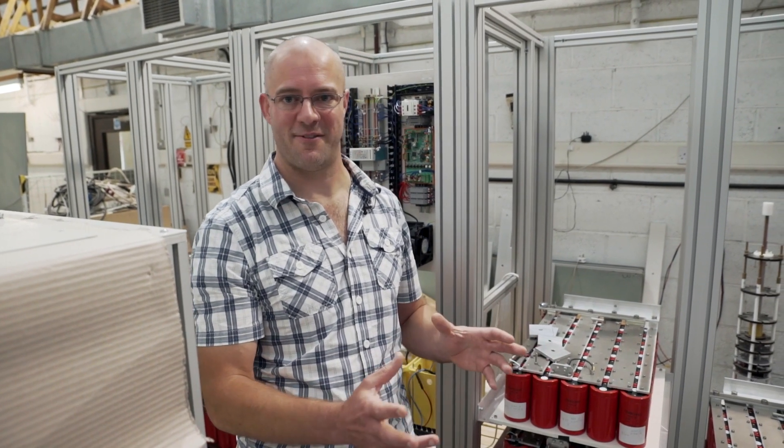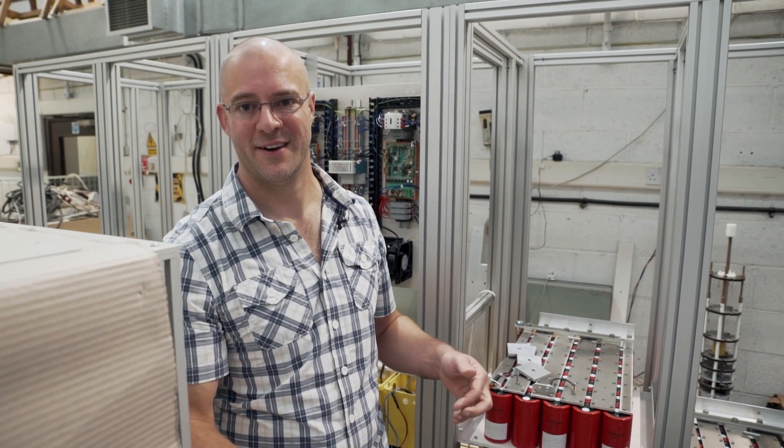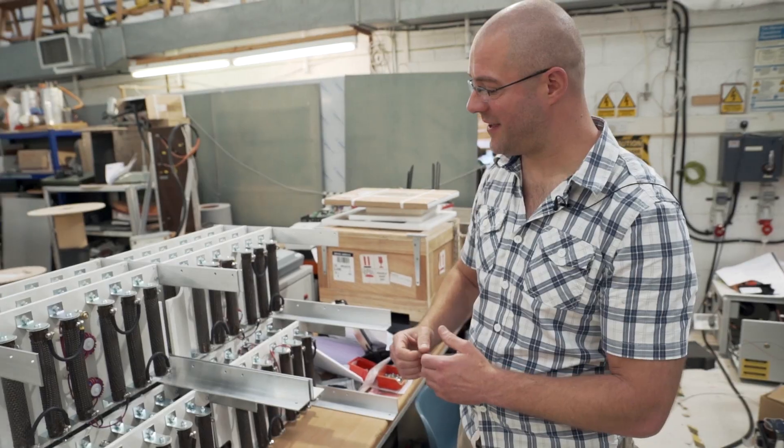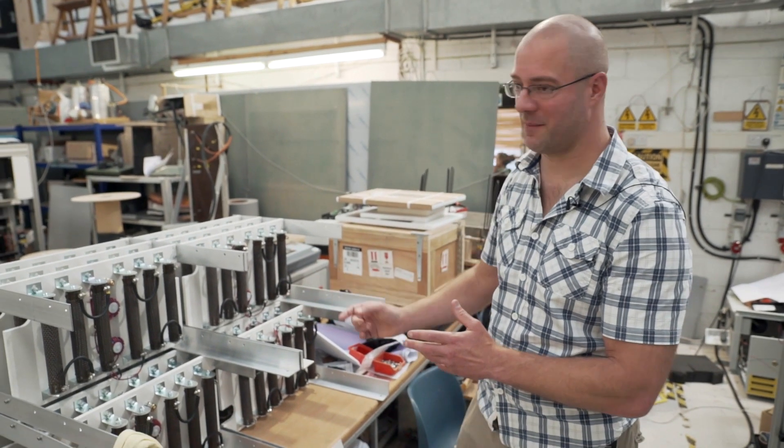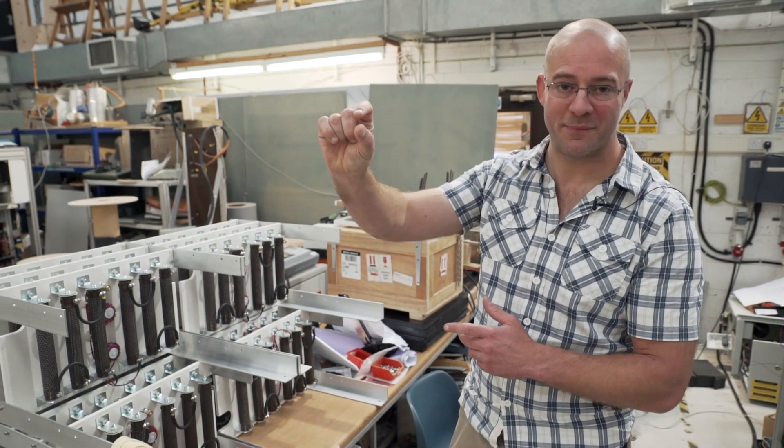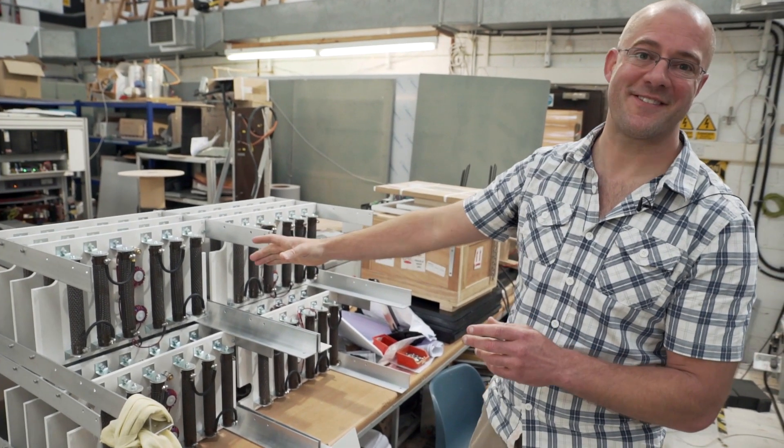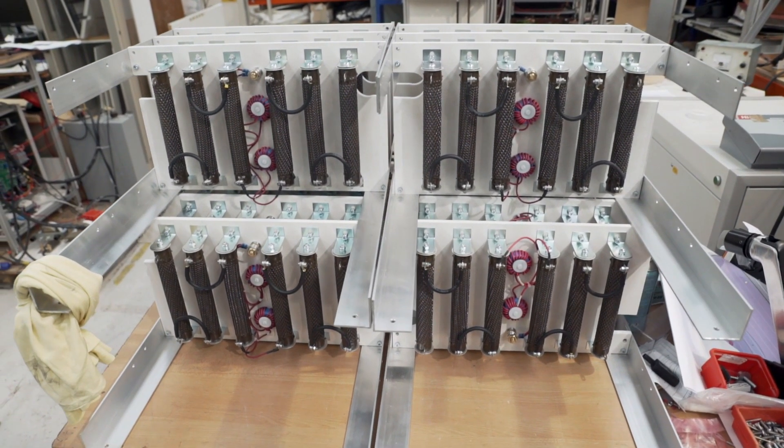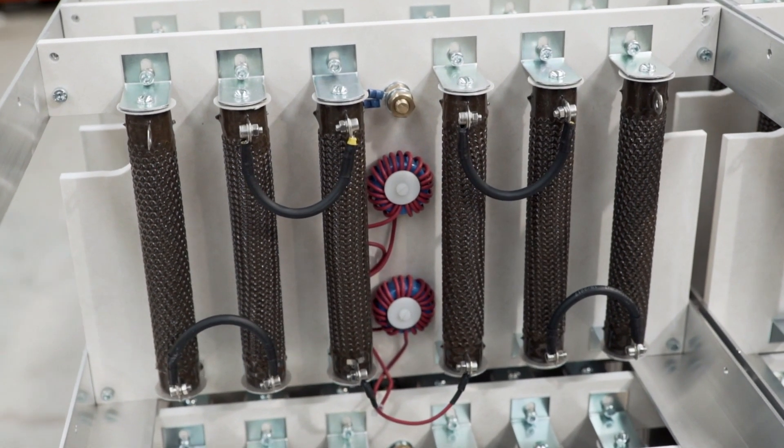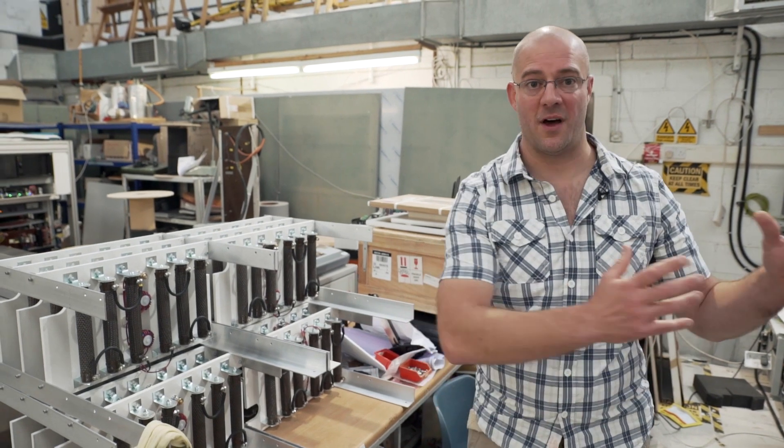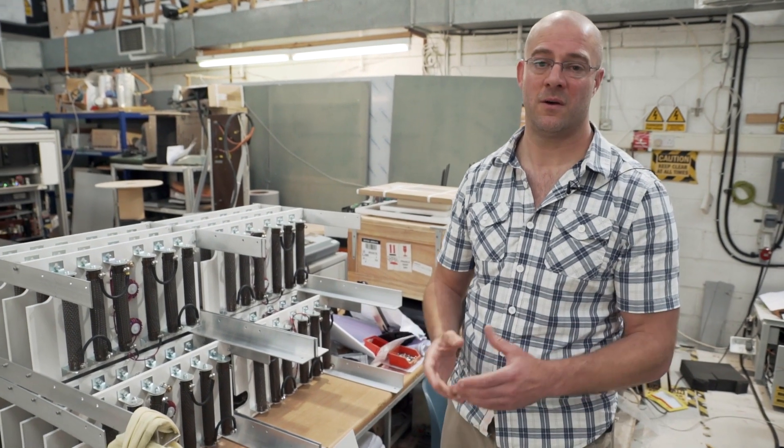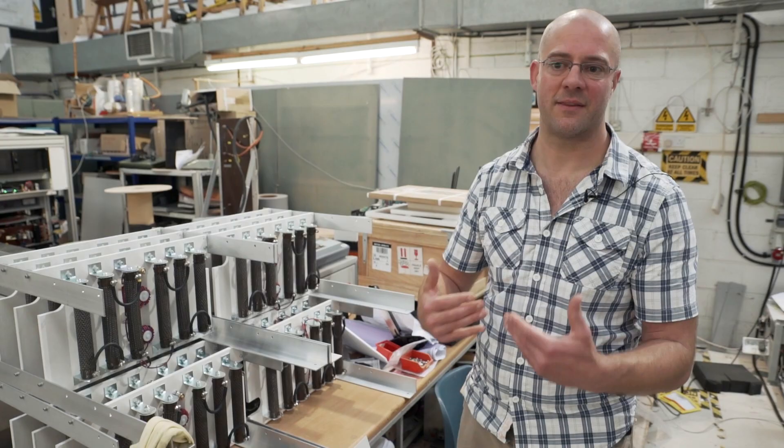So you're left with some stray voltage on the capacitors, maybe 100 volts. And that's a lot, right? I mean, that could really, that could tickle you quite badly. So we also have additional circuitry, which just sucks up that waste charge. And these are just big resistors. So I guess if you've done some electronics, you know what a resistor looks like. It looks like a little cylinder that big, right? Well, these are our resistors. This is where we're dumping the extra charge that the capacitors have. And it just turns it into heat. This is just creating entropy in the universe just to make the machine safe to use. Obviously, that's a big consideration for us. When we're talking about 90 kilojoules at 3000 volts, that's going to leave you smoking in your shoes if you touch the wrong bit. So we have to take very seriously making that safe.